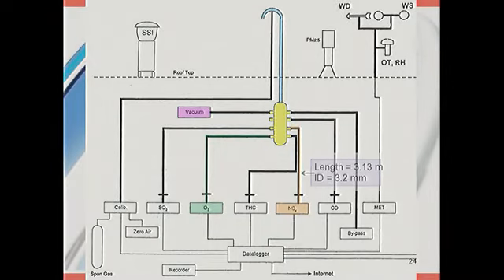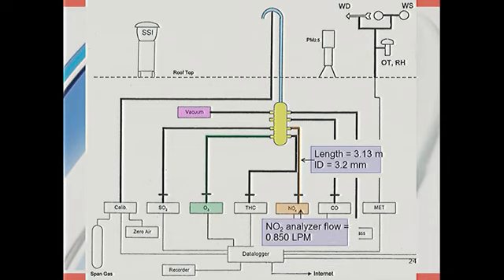So again, we're going to go to NOx. This is pretty much your standard stations out there now, ozone and NOx. 3.13 with the inner diameter of 3.2. Our analyzer's running at 0.850 liters per minute.